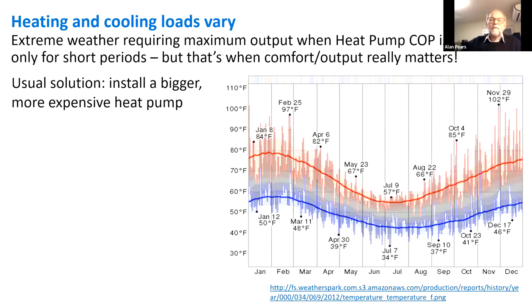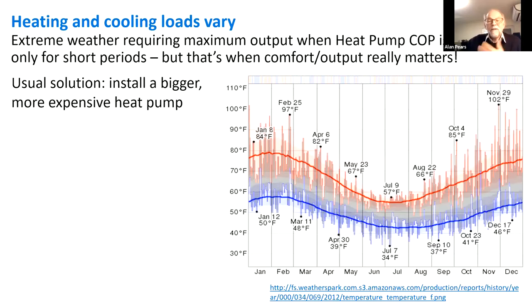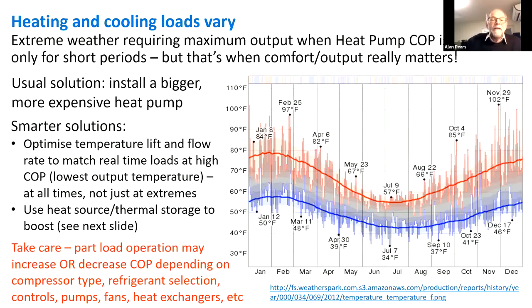If you want an efficient heat pump with high capacity, you want the lowest temperature lift you can achieve. Many air source heat pumps draw ambient air from the local environment — in Melbourne in mid-July there are times around zero Celsius, and under those conditions, if you're trying to provide high temperature heat your COP will be pretty low and you'll need a bigger, more expensive heat pump. However, extreme conditions only occur for short periods, so there are smarter solutions where you adjust inlet and outlet temperatures to maximize efficiency and minimize size.